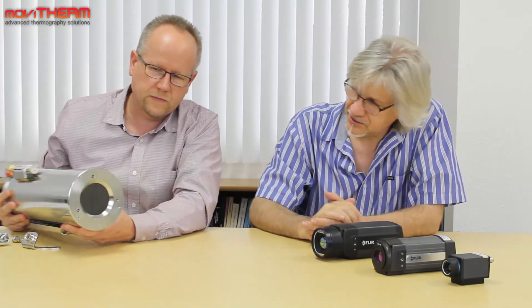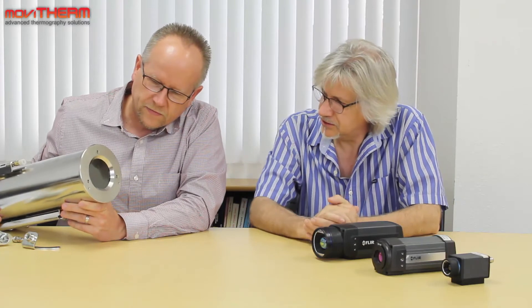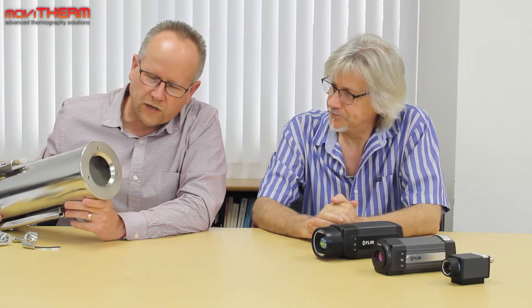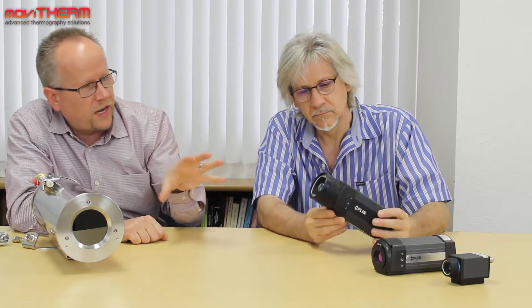We noticed on the front, that doesn't look like just regular glass. One thing to understand when using thermal cameras, these thermal cameras do not see visible light like the human eye in the 400 to 700 nanometer range. These actually see long wave infrared radiation, typically it ranges between 8 and 14 micrometers, very far long infrared radiation. Glass no longer transmits in that wavelength so the manufacturers such as FLIR have to switch over to exotic materials, in this case it's germanium, which this glass window is as well. That's why they have this little purplish kind of sheen in front of it.